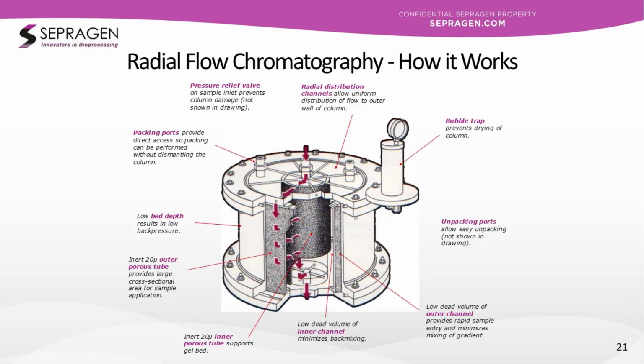And when the column is packed, no more resin will go in. If there's a pressure gauge at the inlet at the outlet of the pump, it'll rise and tell you when the packing pressure hits a certain compaction pressure. That's it, the pump is stopped, and then you can condition your bed by cleaning the lines, running the flow in the forward and then reverse direction a bunch of times, and check your HETP and asymmetry as you might any other column. So very convenient, and these things have been scaled up from little bench scale columns all the way to several hundred liters. And you can do that in one step.